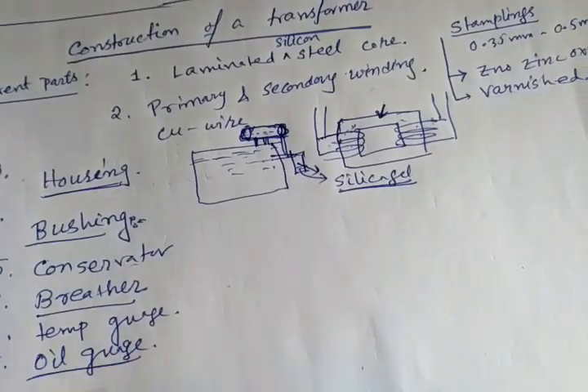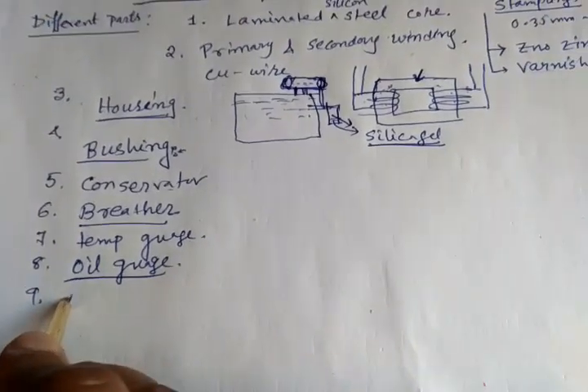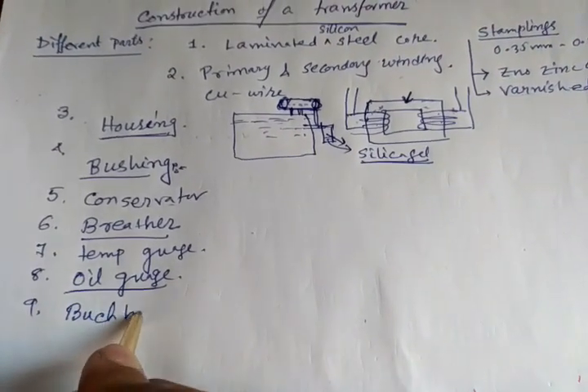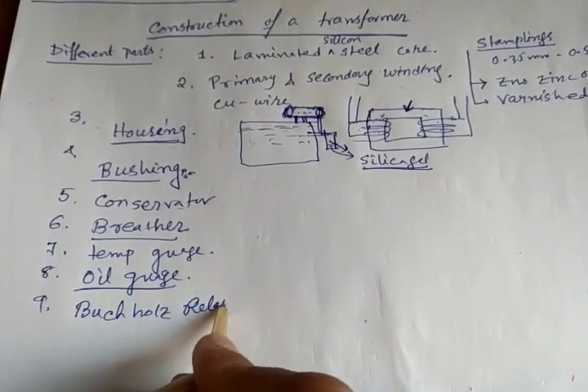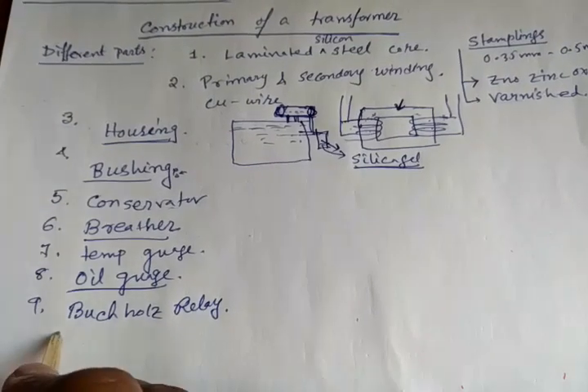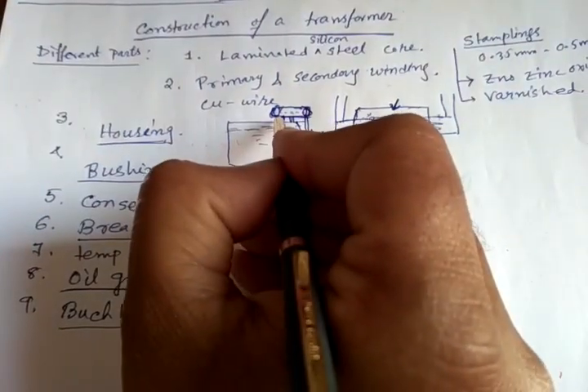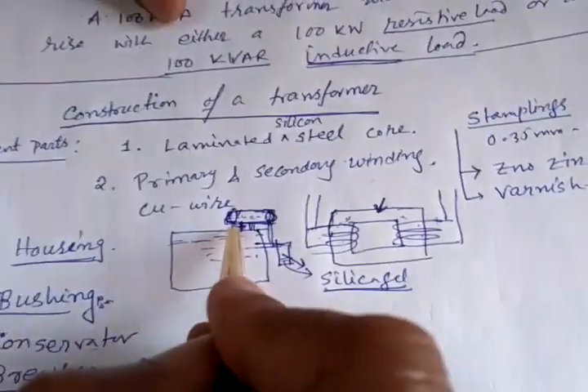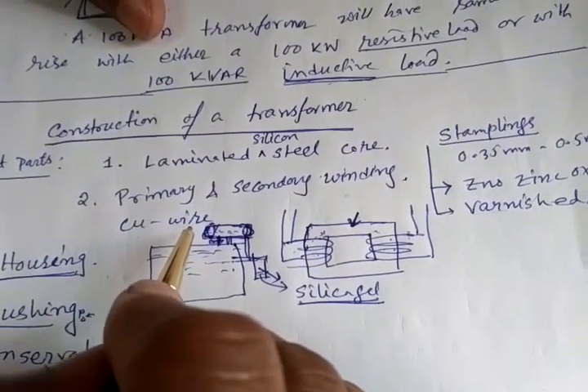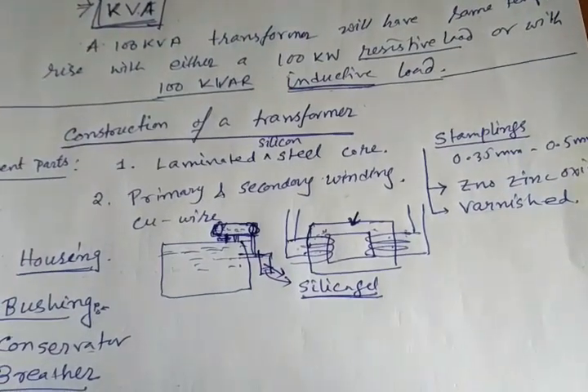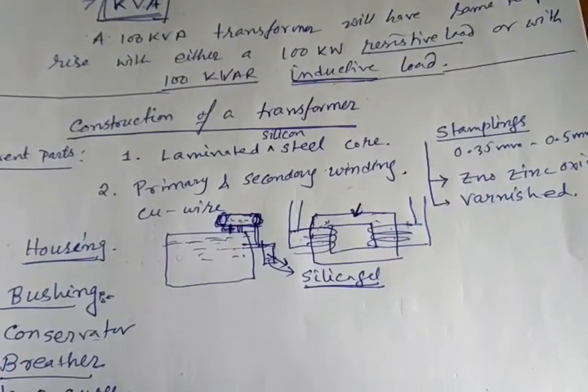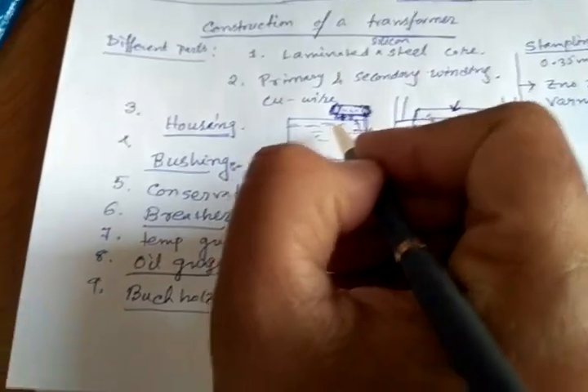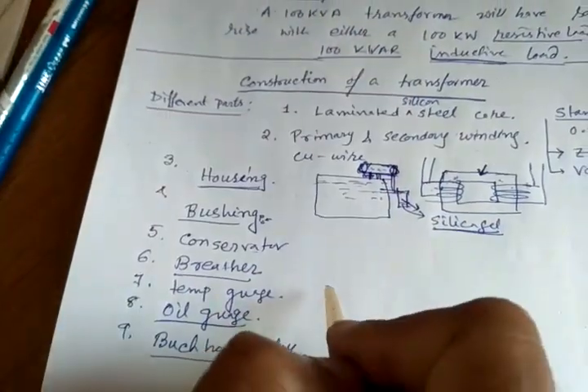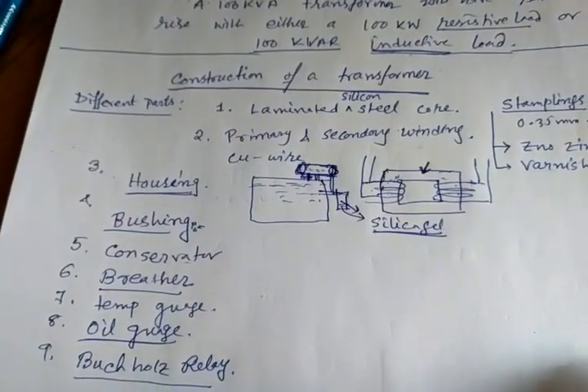And some relay is also used, very important. At least you should know the name of the relay. This is called Buchholz relay. This is basically a gas operated relay. In the middle, the conservator is connected to the tank, and in the middle this Buchholz relay is connected. This relay identifies any presence of gas in the transformer oil, and if some serious fault occurs, then gas is produced, and in that case this relay disconnects the transformer from the circuit.